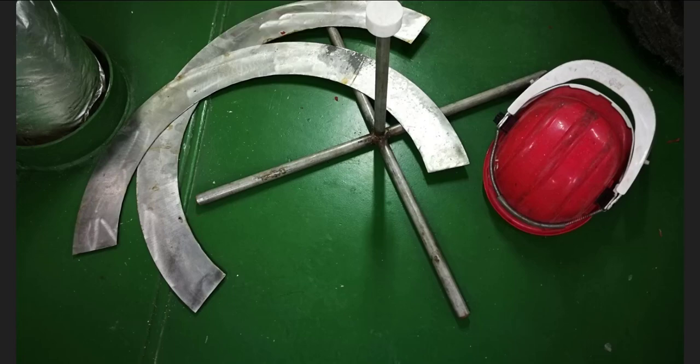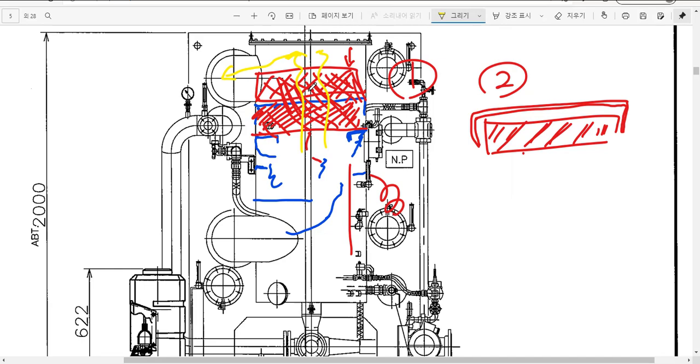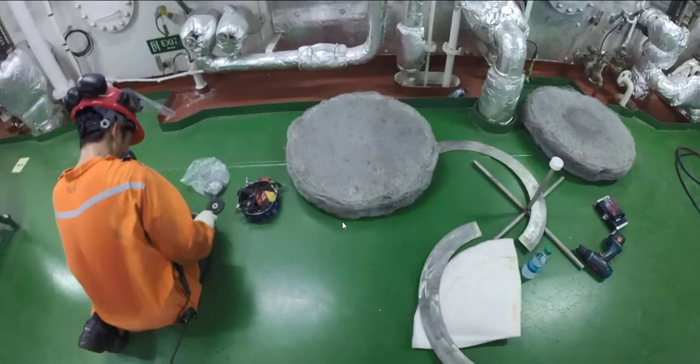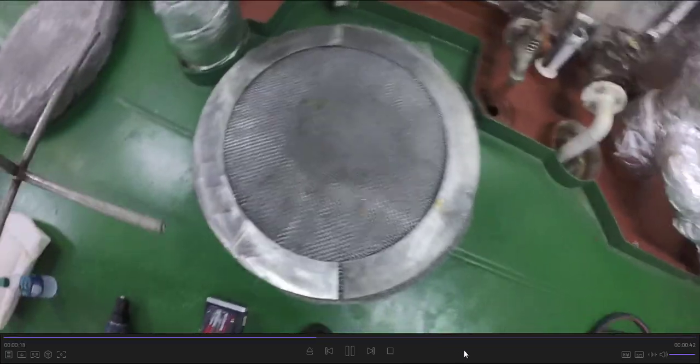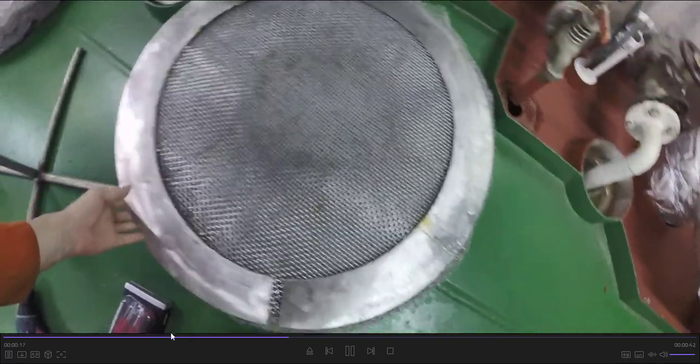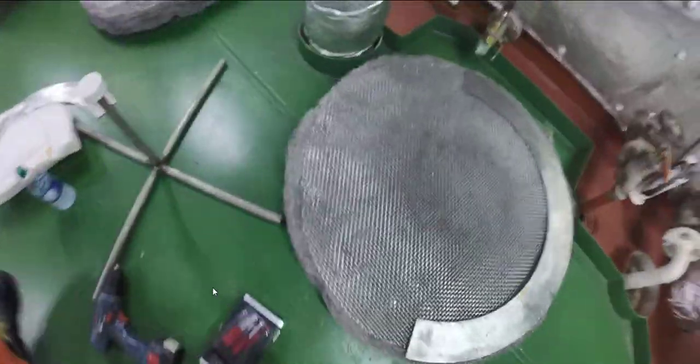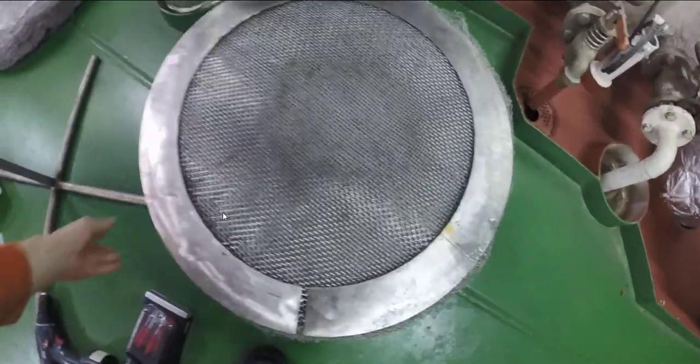This is what I prepared because I want to compress the demister filter, fully compressed. If this mesh filter is not compressed and fine, the water mist will pass out. If it passes out, this water mist will increase the salinity. You must make sure this mesh filter side and also screen out here. If you have any question, reply me, write down. That's it.